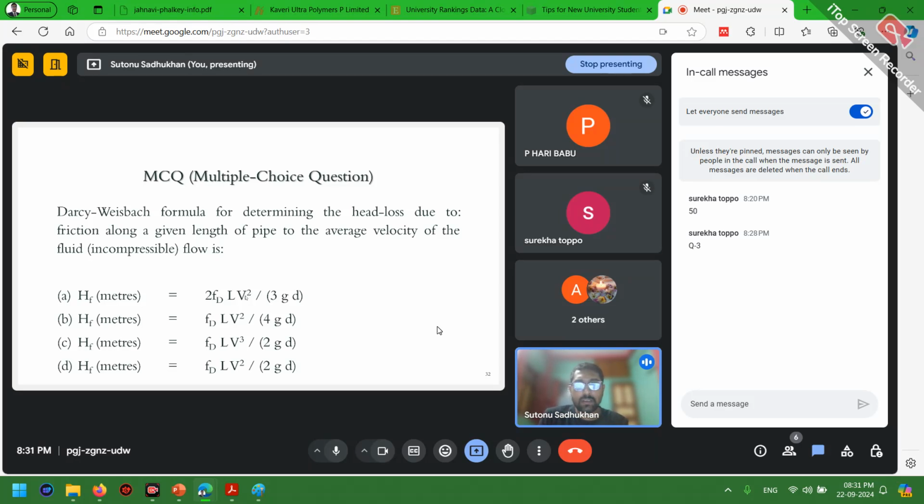So Q is dependent on, if it is a heat exchanger, then the flow rate of water will be determined with the help of the m Cp delta T. But that is not our concern here. Here our concern is the H, that is the pressure drop. Mostly, if there is no bend, only a straight line, and you are supplying the water to a certain distance, so length is involved, then the Darcy-Weisbach equation is the formula with which you calculate the pressure.